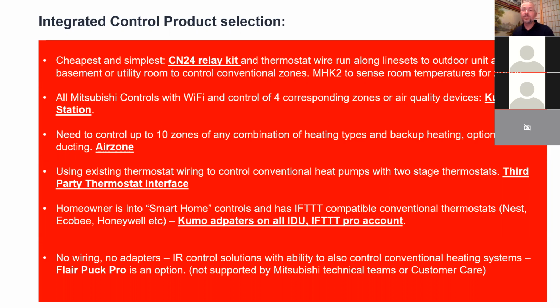You do have the ability to set a switchover temperature in Kumo station, but my recommendation is to set that to never and always have the heat pump in operation. Don't be swayed by economic balance point. It's just not that great. You can actually contribute to worse efficiency depending on how the settings are relative to that house. If you need something really more sophisticated, a high-end home, they're looking for the premium product that has touchscreen capabilities, possibly Wi-Fi, many zones, many different styles of heating systems, Airzone can accomplish things that no other controller from any other manufacturer can, as far as I know. And then, of course, there's third-party thermostat interfaces, which can make for a very simple interaction for the consumer.